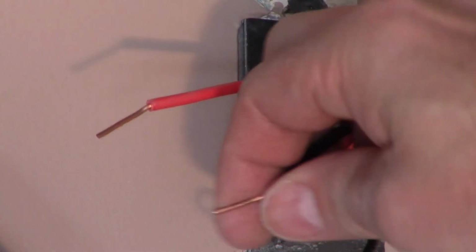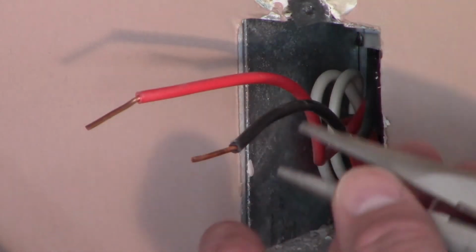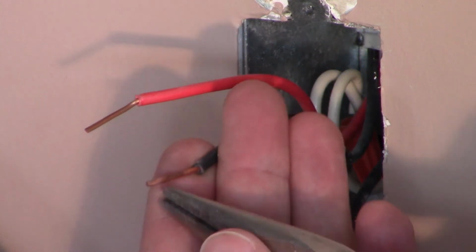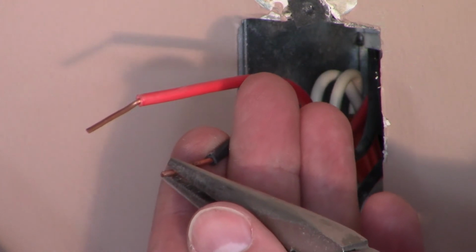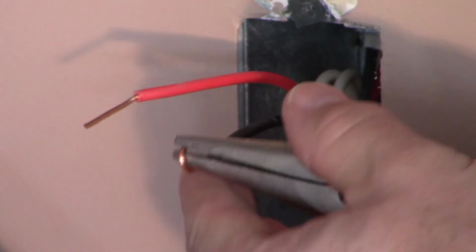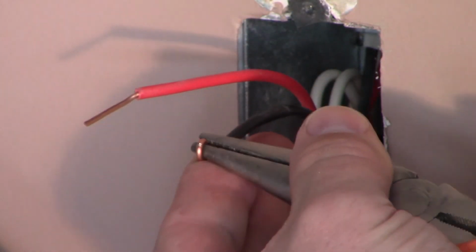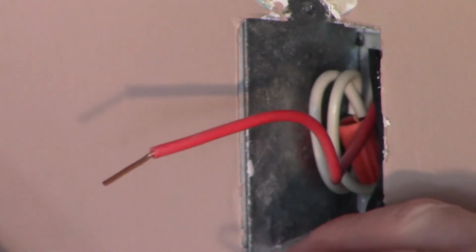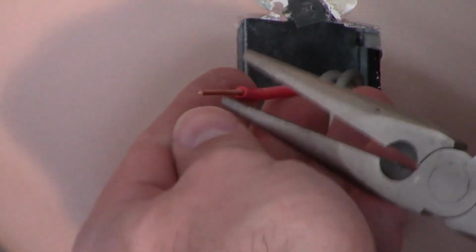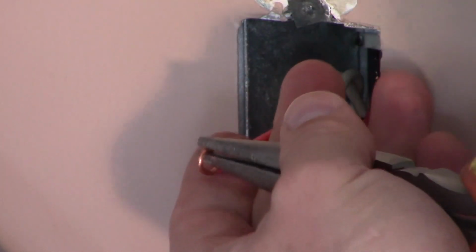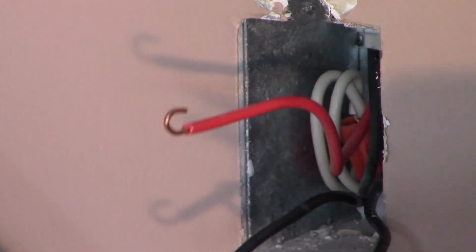So we do that to all the conductors. Again, just leave a little bit at the end of the pliers there. Oh, I'm a little clumsy. First day with my thumbs, sorry. Grab on and just turn the pliers all the way around, and then back just a little bit, all the way around and back just a little bit. It makes that beautiful little loop. I find 5/8 is the magic number. If you can strip 5/8 of wire off, then you've got it just about bang on.